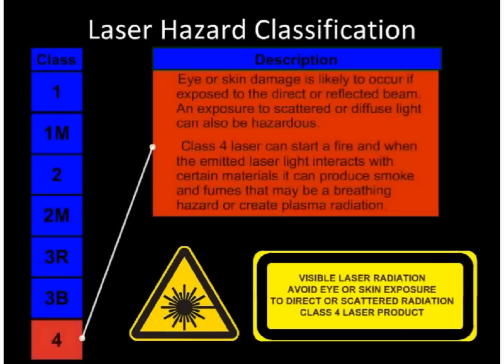Class 4. Eye or skin damage is likely to occur if exposed to the direct or reflected beam, and exposure to scattered light can also be hazardous. Class 4 laser light can start fires, and when the emitted laser light interacts with certain materials it can produce smoke and fumes that may be a breathing hazard. In some cases it can even create plasma radiation.